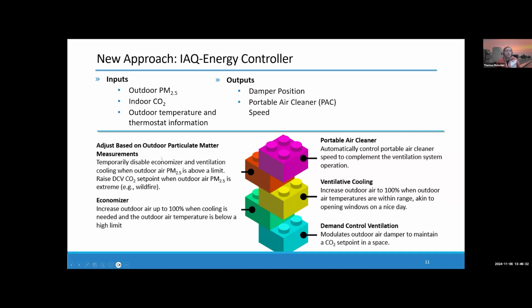And then finally, it's going to consider outdoor air quality. And when outdoor air quality is poor, it's going to raise the CO2 set point that's operating on the demand control ventilation piece. And then a portable air cleaner is going to change speeds so that the combined ventilation and filtration from the central system and the portable air cleaner is maintaining a minimum air changes per hour for removing respiratory aerosols that we're all breathing that meets the ASHRAE 241 standard for control of infectious aerosols.